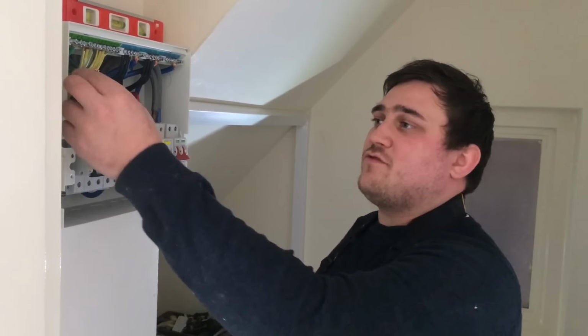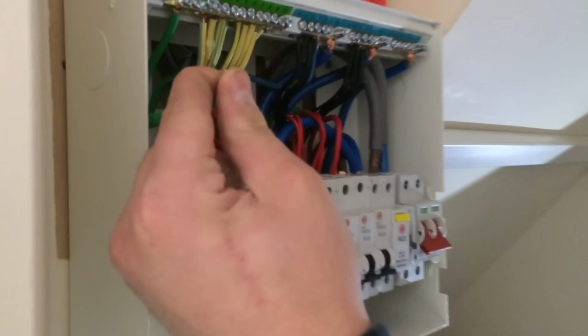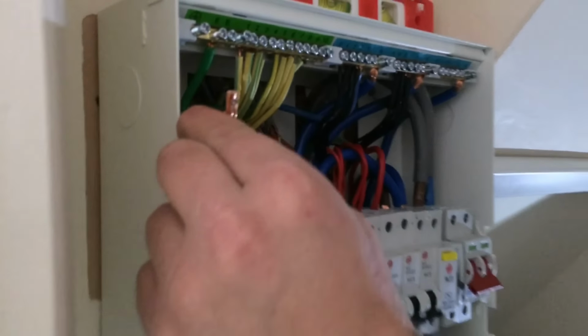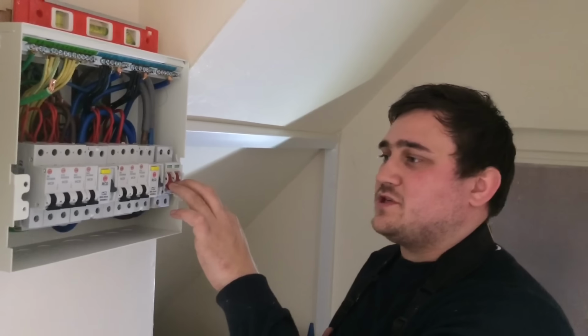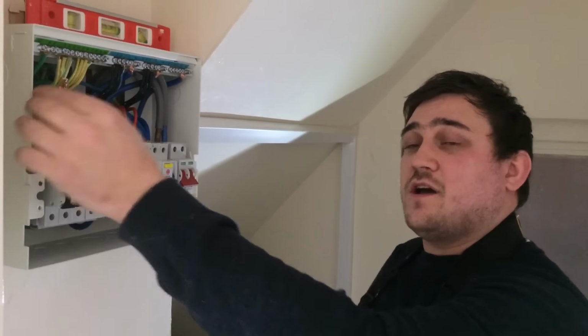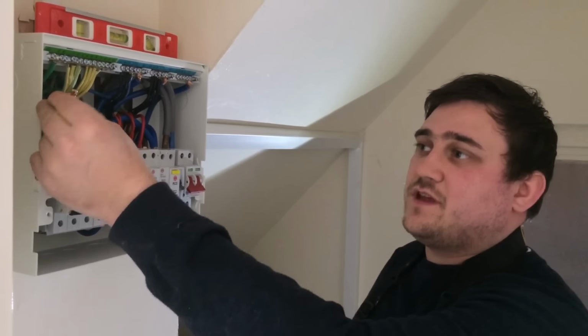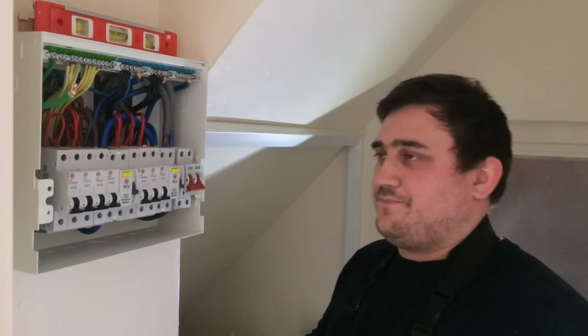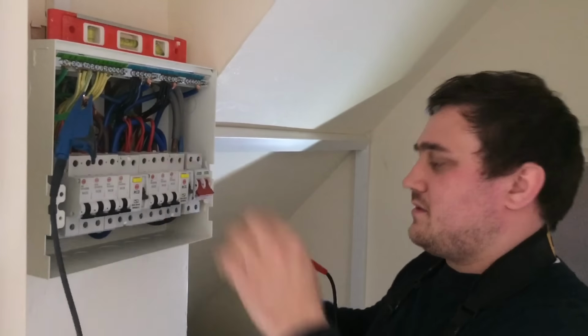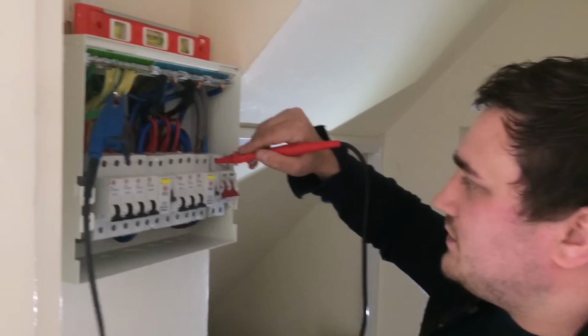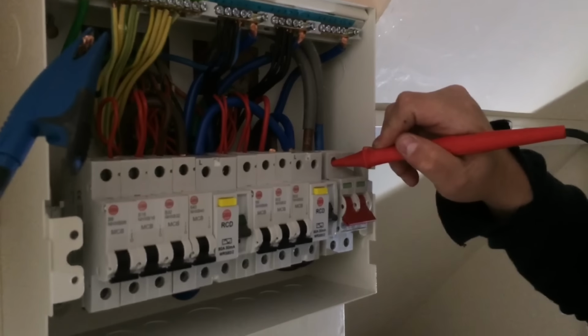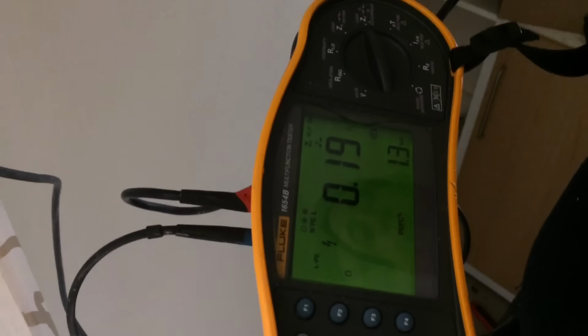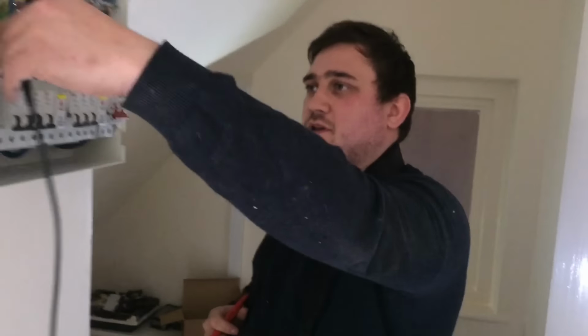We're now doing our external earth fault loop impedance test. For this I've removed the main earthing conductor from the board. This is to eliminate the parallel earth paths. I've also switched the installation off by the main switch in the board, just in case anything becomes live under fault conditions. While we have this removed, there would be no earthing to it. We're going to clamp on to our earthing conductor, and in the top of the main switch we're going to go onto the line conductor and receive a reading of 0.19 ohms. That is satisfactory because we have a TN-C-S earthing arrangement and the maximum Ze for that is 0.35 ohms.